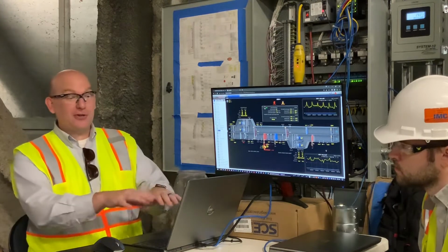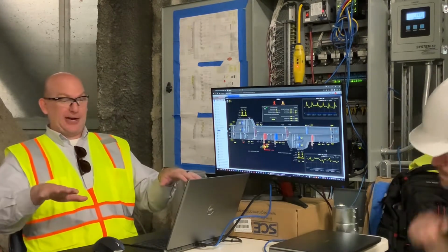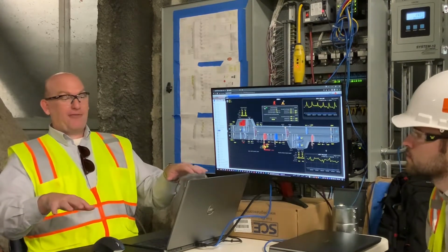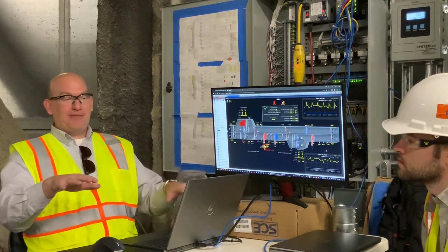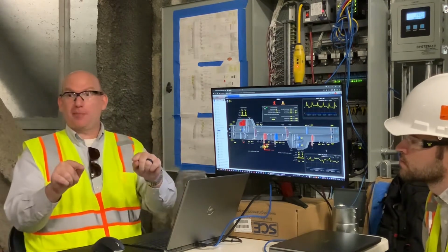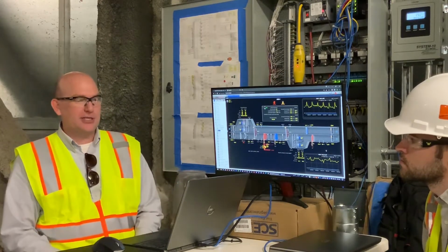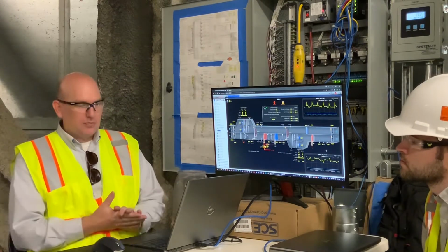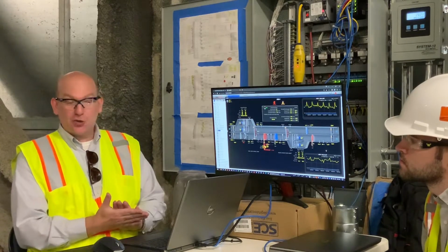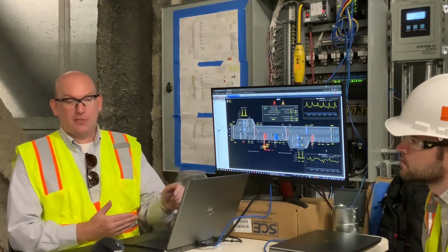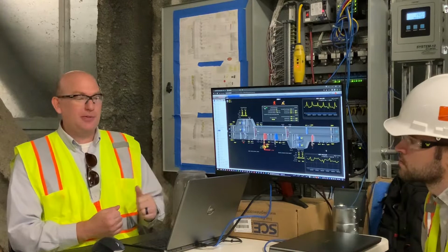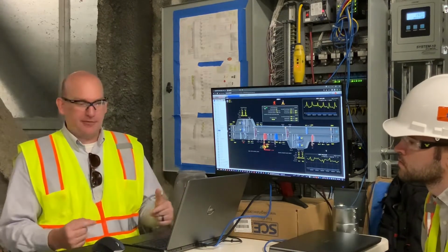Now if they're disconnected, you have air handler 1 and air handler 2, and their fan speeds are going to start to drift. If they drift too much serving the common plenum, it can cause vibrations and problems in airflow in the system. So there's some safety built in. As soon as it happens, the unit will throw an alarm. It'll tell you guys that there's a problem, but it'll keep delivering air.